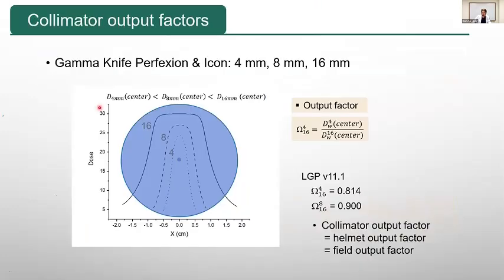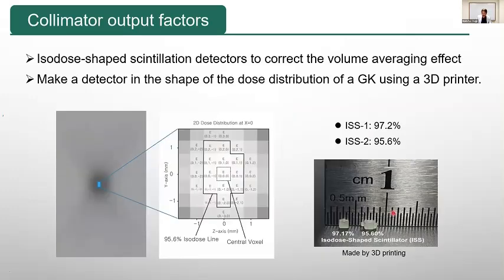And regarding the dose rate of GammaKnife, there is another factor called the collimator output factor. The collimator output factor is the ratio of the dose at the center of a collimator to that at the center of the 16 millimeter collimator. Some people say collimator output factor, others say helmet output factor, and it is field output factor in many cases. And the Leksell GammaPlan, the most recent one, uses 0.814 for 4 millimeter and 0.9 for 8 millimeter. And it's a very interesting task for medical physicists to check these values experimentally.